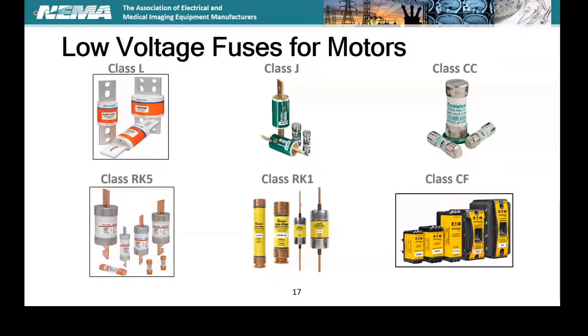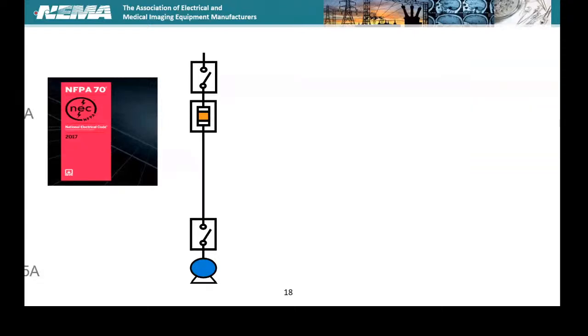All right. Next slide. So in this case here, we have motor overcurrent: short circuit protection and overload protection. So we're going to try to come up with an example. Can I use a fuse to do both of them? Can I use a fuse that meets the allowance set up in the code in 430 for overload protection, and then have that also meet our short circuit protection? And I say short circuit, and we all know that it says ground fault, blah, blah, blah. I just say short circuit protection. The code wants to give it this nine-word description for that first fuse in line.